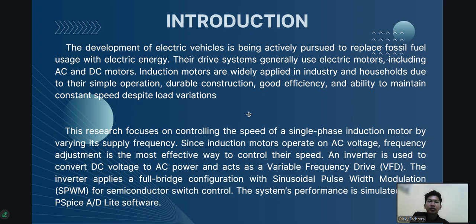The speed of the induction motor is greatly influenced by the frequency of the AC voltage source. Therefore, frequency regulation is the most effective method to control the speed of the induction motor. In this study, an inverter is used that functions as a variable frequency drive or VFD to convert DC voltage into AC with a frequency that can be adjusted.